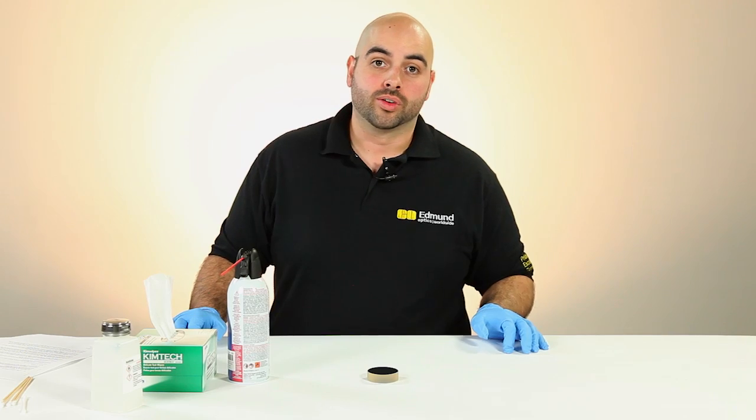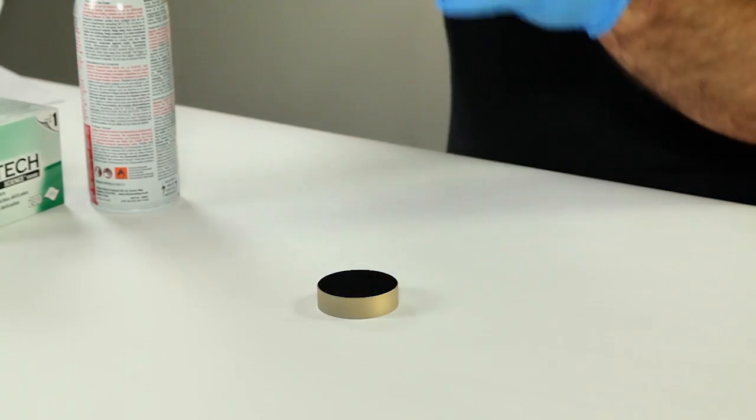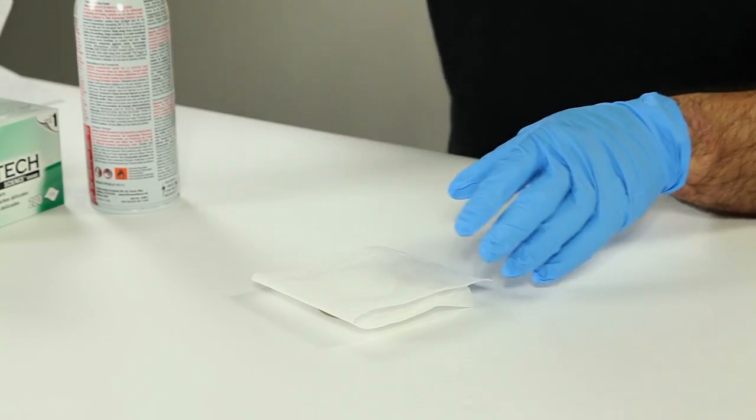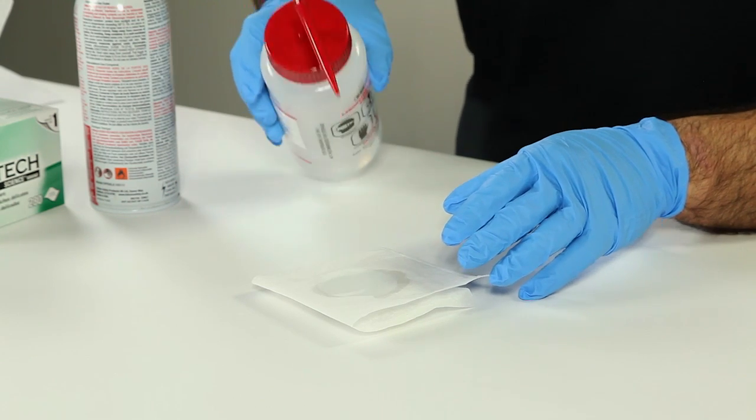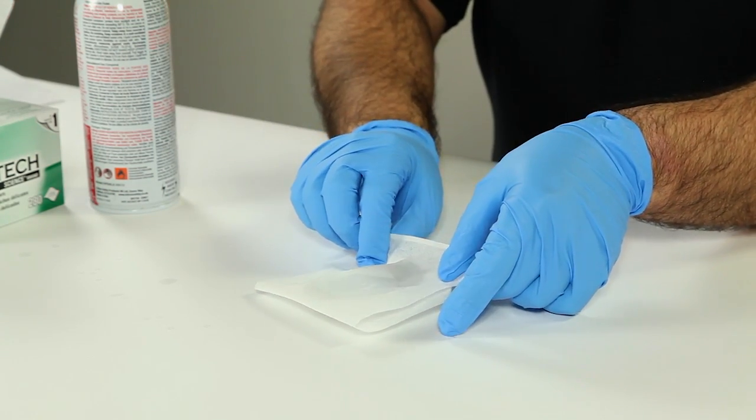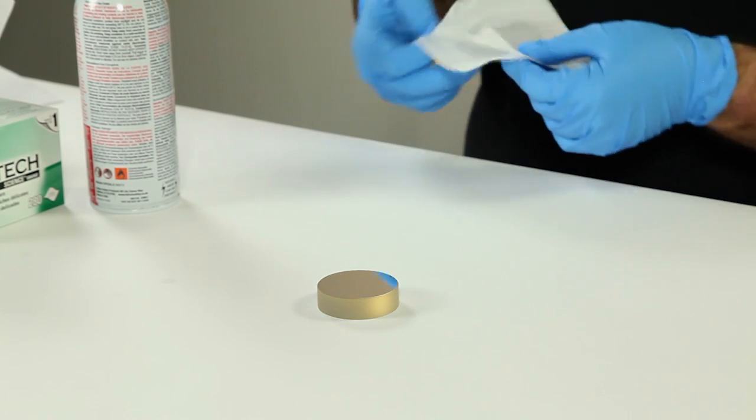Rather, for large flat optics like this, the lens tissue should be placed over the optic surface. Moisten the lens tissue with a few drops of acetone or alcohol and then drag the tissue across the surface. You will see the solvent evaporate as the tissue is removed. For best results, avoid overly saturating the tissue.